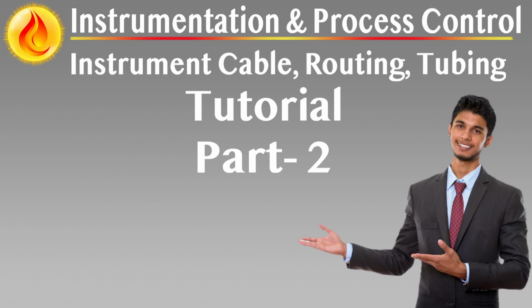Cable joining procedures for underground installations must be fully defined and approved, including materials, joint integrity testing, labeling, and inspection criteria. Special attention is required at building entry points, where cable support structures must be designed to accommodate long-term soil settlement. Transition structures or wall sleeves should be employed to prevent stress or mechanical fatigue at critical entry interfaces.